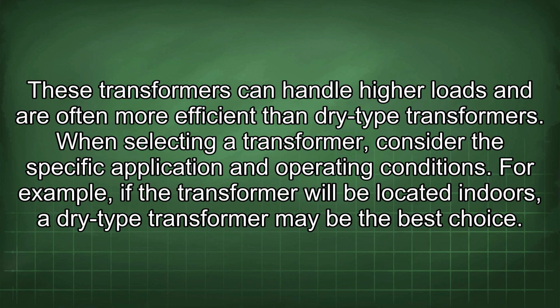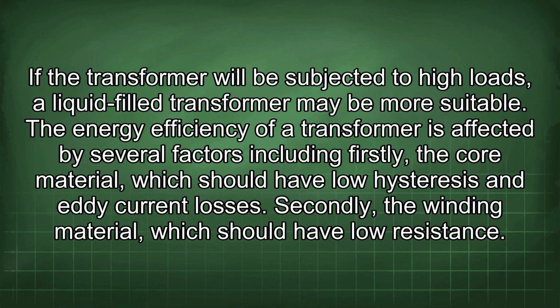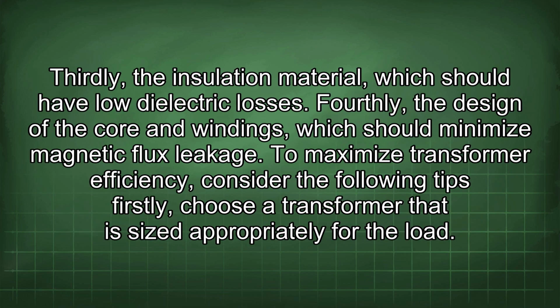When selecting a transformer, consider the specific application and operating conditions. For example, if the transformer will be located indoors, a dry-type transformer may be the best choice. If the transformer will be subjected to high loads, a liquid-filled transformer may be more suitable. The energy efficiency of a transformer is affected by several factors, including firstly, the core material, which should have low hysteresis and eddy current losses. Secondly, the winding material, which should have low resistance. Thirdly, the insulation material, which should have low dielectric losses. Fourthly, the design of the core and windings, which should minimize magnetic flux leakage.